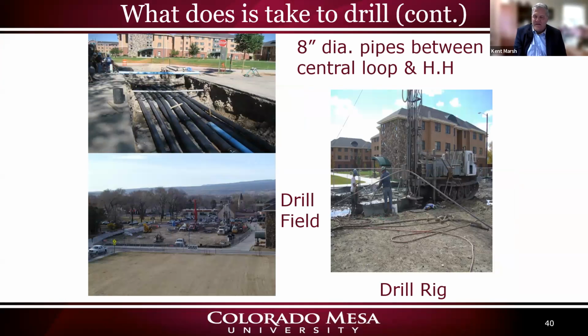Our drill field is installed deep enough beneath the ground to prevent us from having to use glycol. We have many hundreds of thousands of gallons of water in our system, and we didn't want to add glycol to prevent freezing, so we make sure we install below the frost depth here in Western Colorado.